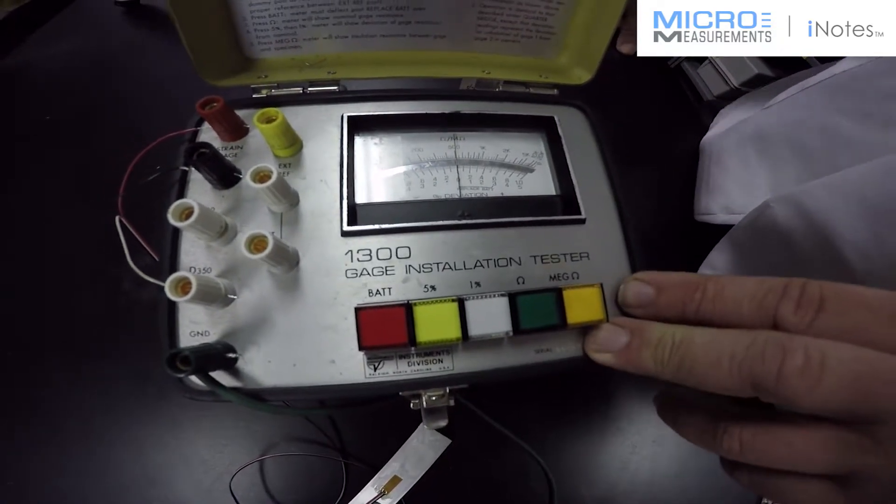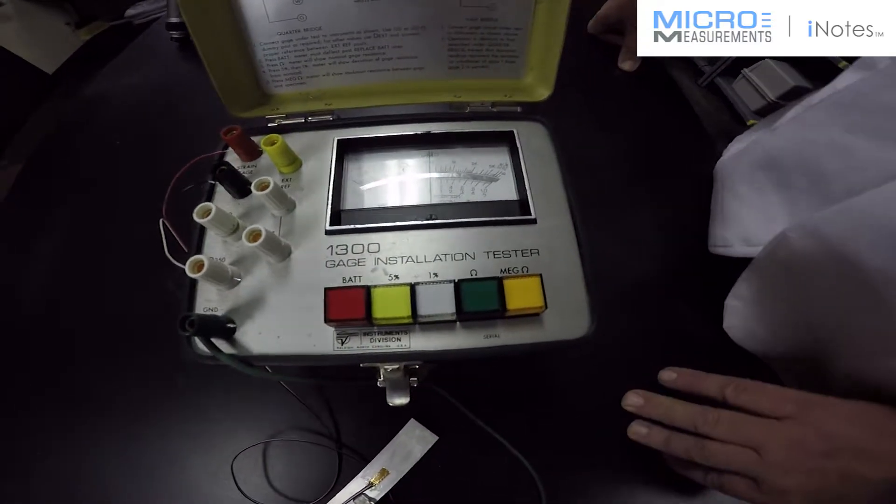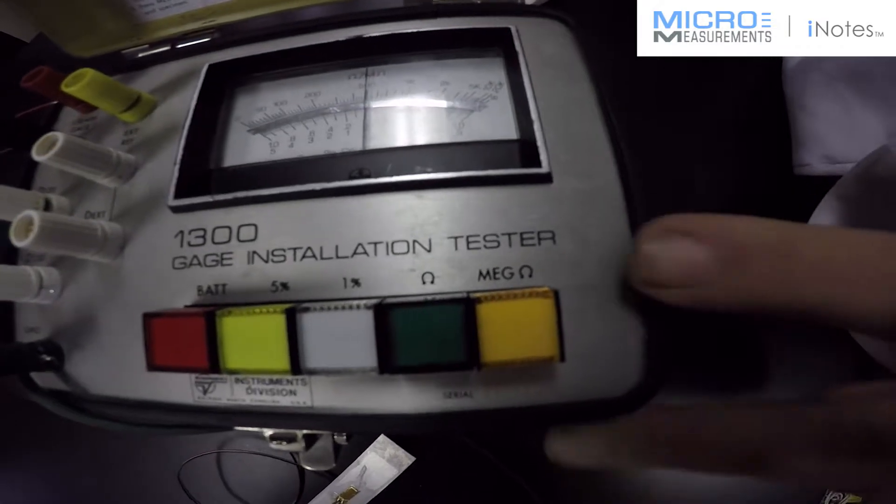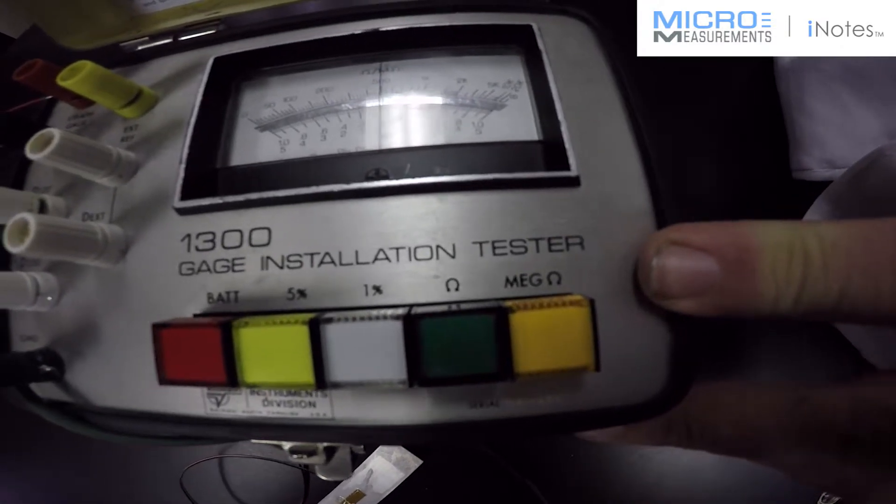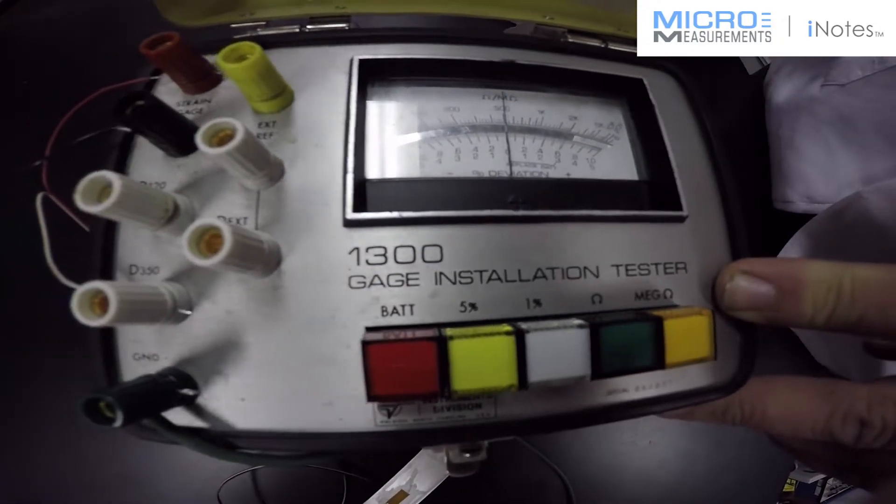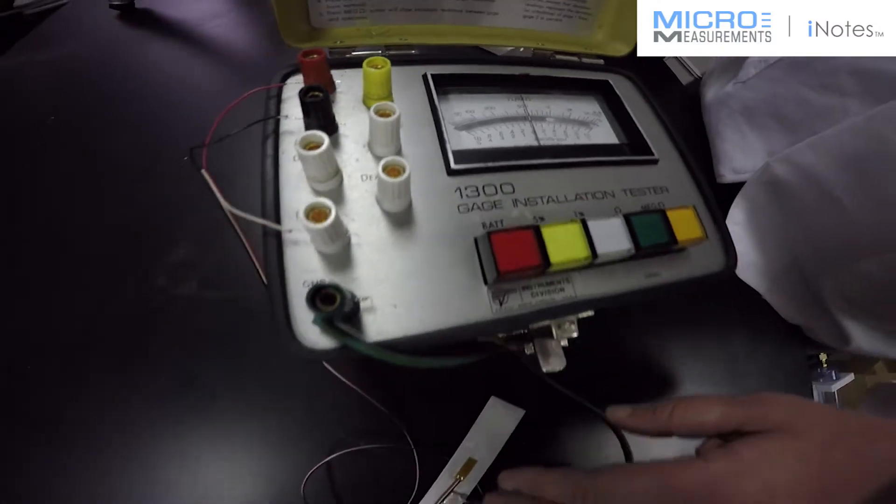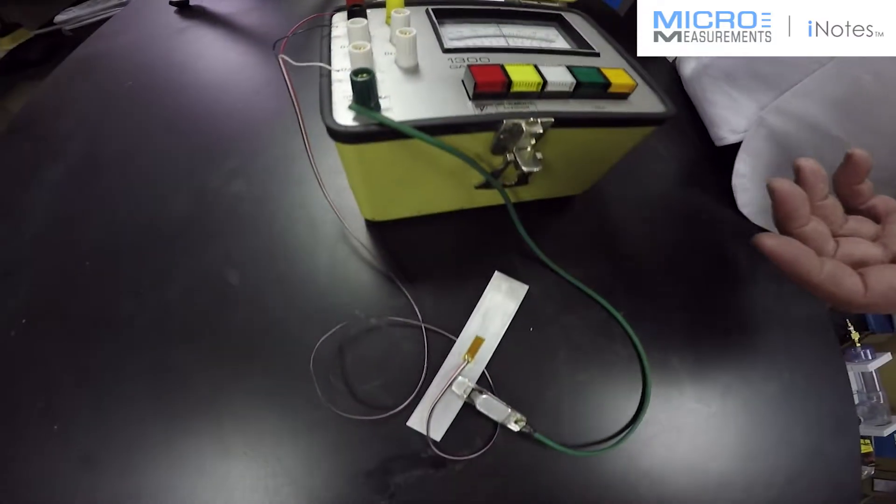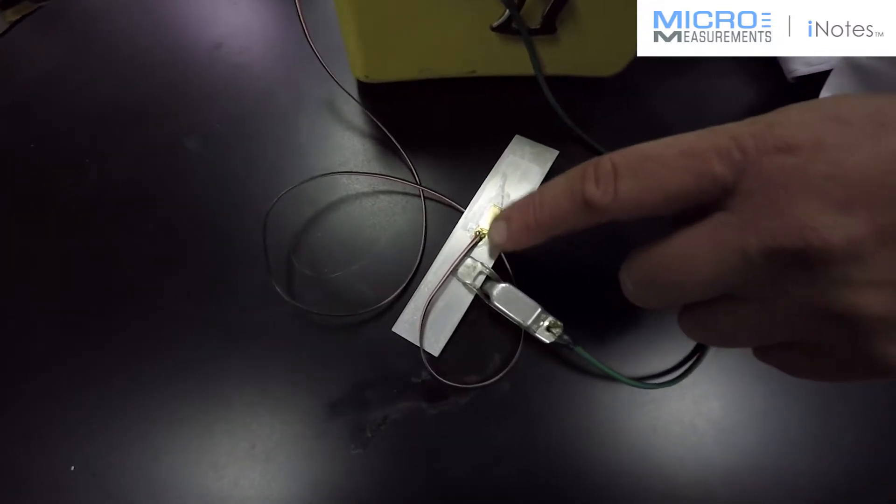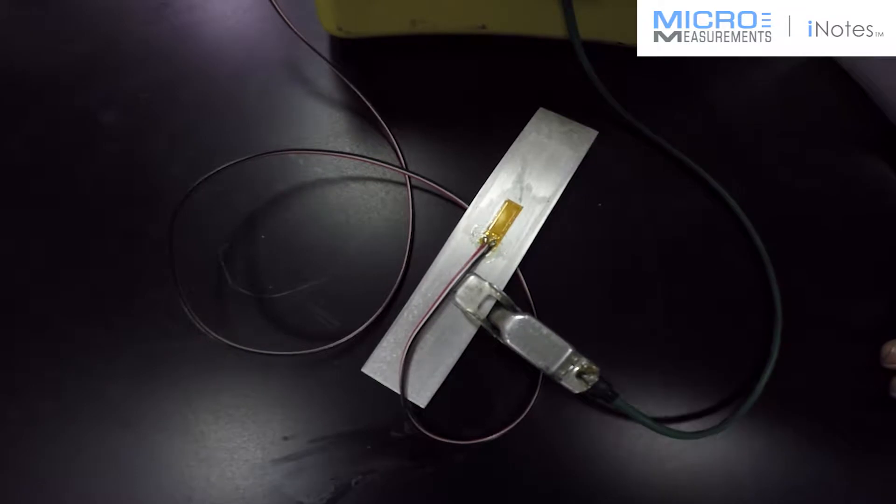Now, the really nice feature of the Model 1300 is it has a mega ohm feature. And most commercial mega ohm meters are going to use a very high voltage to check resistance to ground. You don't want to put a high voltage across your strain gauge because anything over about 100 volts - these mega ohm meters can typically use 250 to 500 volts - there's a good chance of arcing. The insulation strength of a strain gauge is typically around 100 volts.